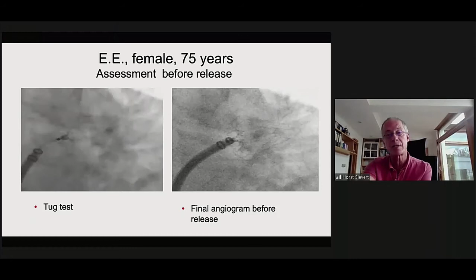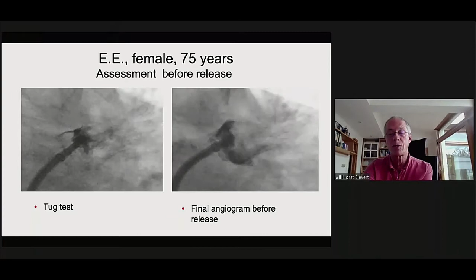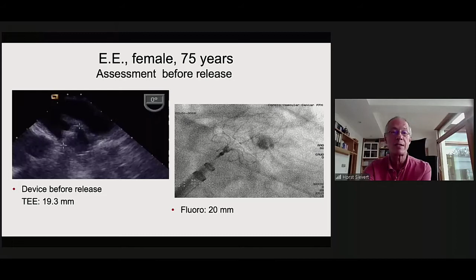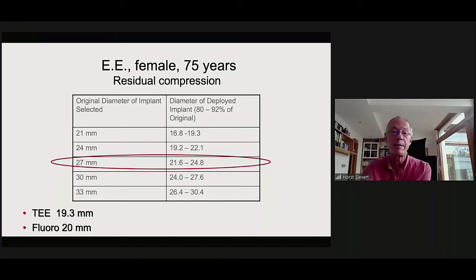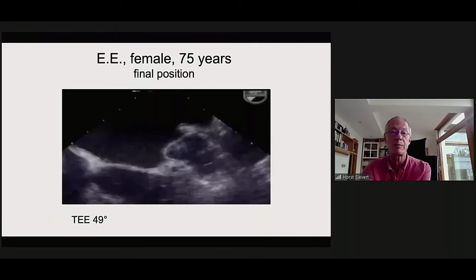This is the final angiogram before release. So we look for the proper position. This is compression, device measurement on compression: on TEE 19 millimeters, on fluoro 20 millimeters. So residual compression was okay. We are looking for at least 10% residual compression. This is the final position of the device.